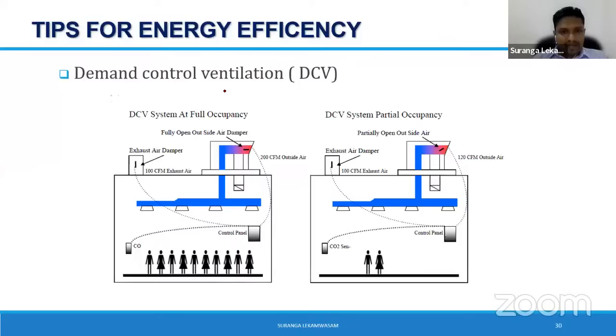Then demand control ventilation, because as I told you, to comply with the IAQ level, you have to supply fresh air sufficiently, and obviously sufficiently. But again, supplying fresh air is a headache because it consumes huge energy to cool. Therefore, you can introduce a little bit of controls to adjust the amount of fresh air that you add according to the requirement, right? Why do we need fresh air? It is to maintain the CO2 level, probably.